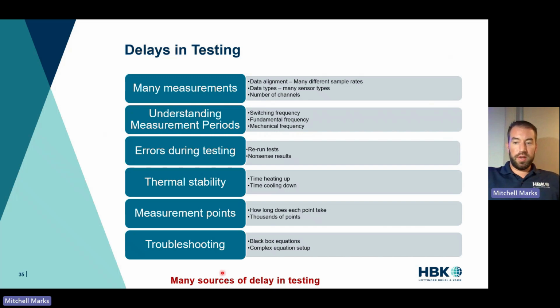So what are some sources of delay? I won't read through all of these points, but you're making a lot of measurements with different data types, different numbers of channels, different alignments, and this is taking time to process. I've talked about cycle-based measurement. If you start measuring on weird periods for different instruments, you start seeing wrong results. If you start filtering poorly, you start seeing wrong results, and you end up ghost hunting because of your instrumentation. If you have errors, if you set a filter wrong, you might need to rerun tests. The machine heats up and it needs to cool down. We do these efficiency maps at a very fixed temperature, so you end up waiting on thermals. Each measurement point takes time, and when you're doing thousands of points, seconds add up. And then troubleshooting. Nothing ever goes right the first time. So there are many sources of delay in motor testing.